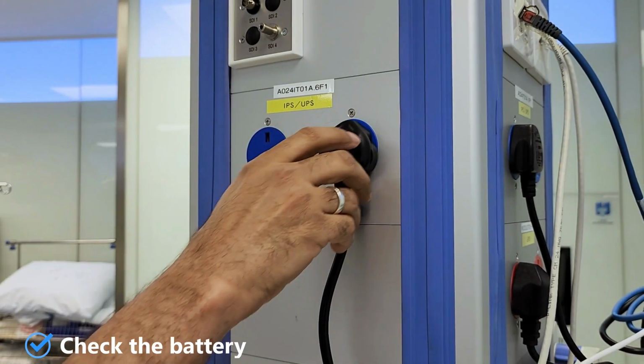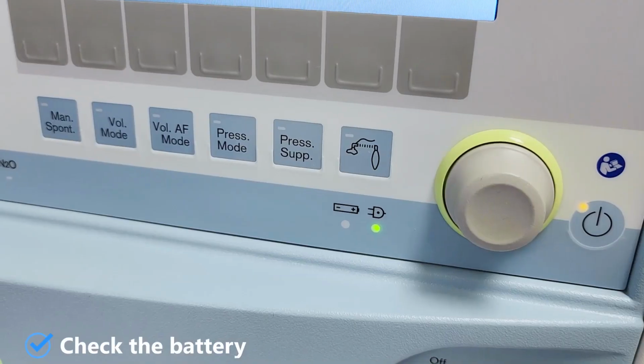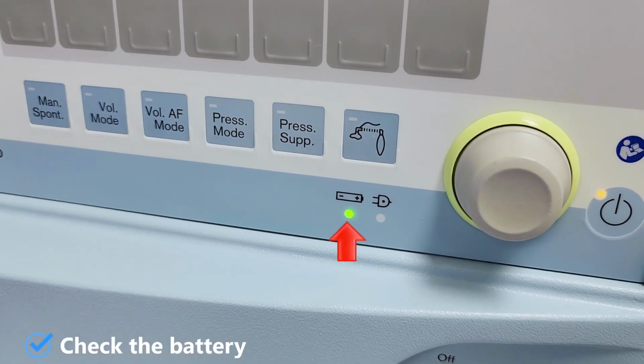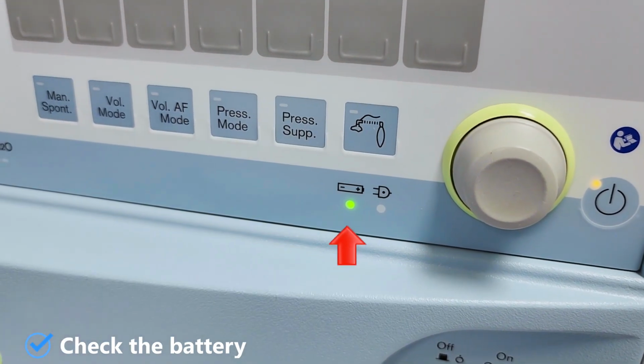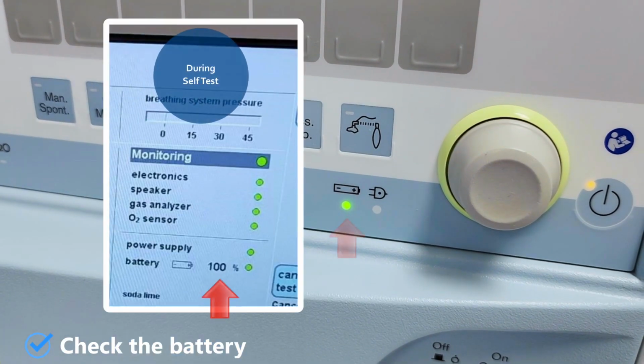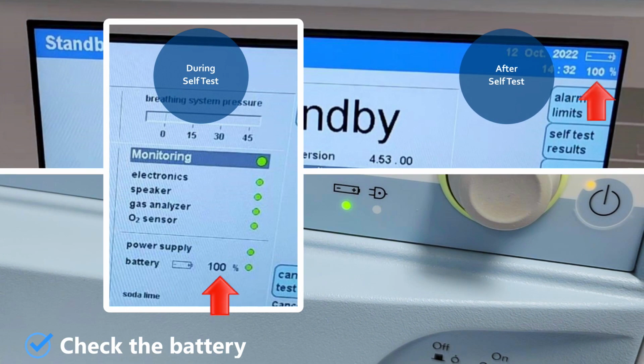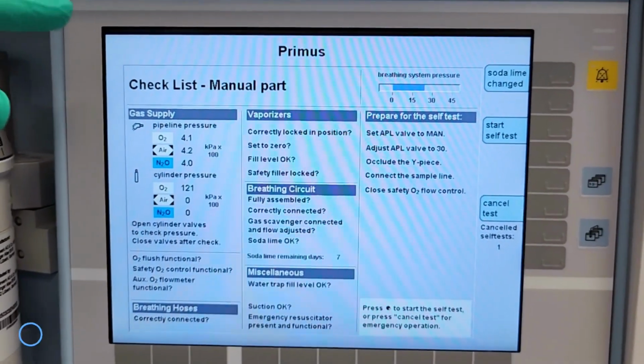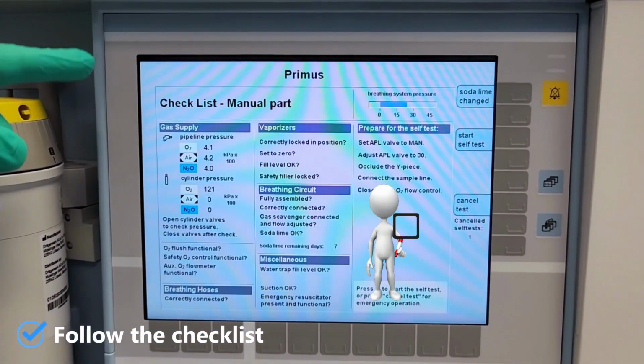Now to check whether the battery is functional. Disconnect the power supply and make sure the LED indicator for the battery shows green. Also, the percentage of the battery will be visible on the top right corner of the screen during and after the self-test. Once the machine is on, we can see a checklist that we have to follow one by one.